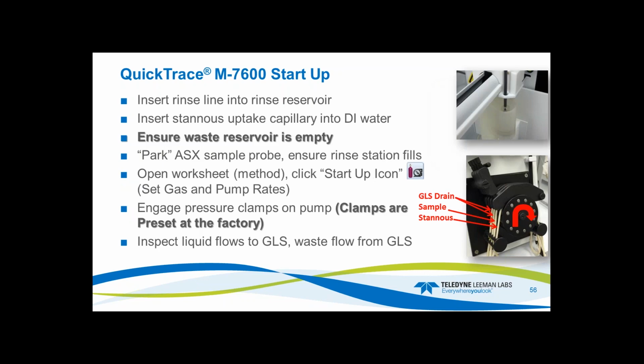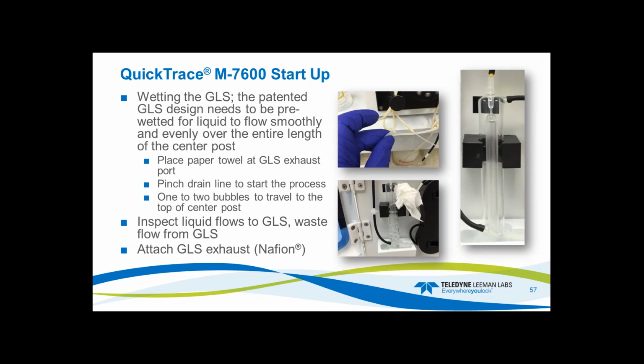You want to insert rinse line into the rinse reservoir, insert the Stannous uptake capillary into the DI water. Again, ensure your waste reservoir is empty. Then you park the probe. That'll start filling the rinse station. Open the worksheet that you want to run, new, from, open, what have you. Click the startup icon. It'll set the pump rate and the gas rates to match what's in that worksheet. Engage the pump clamps, and then inspect the liquid flow to the GLS and from the GLS to the waste.